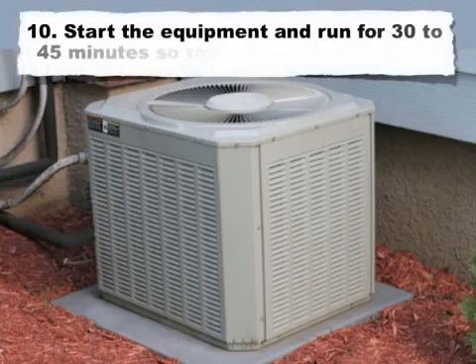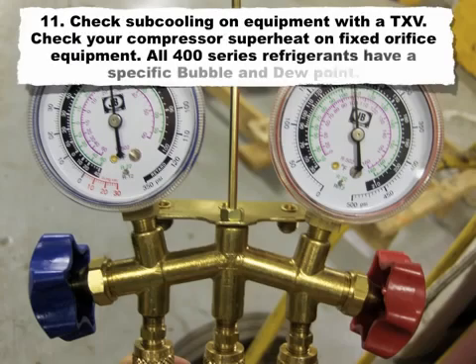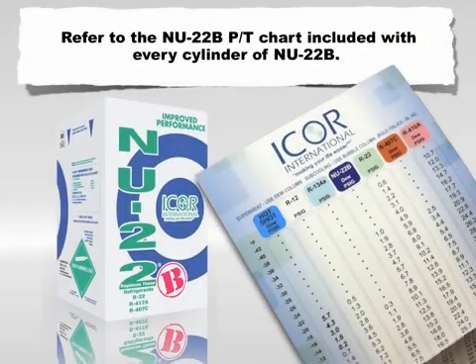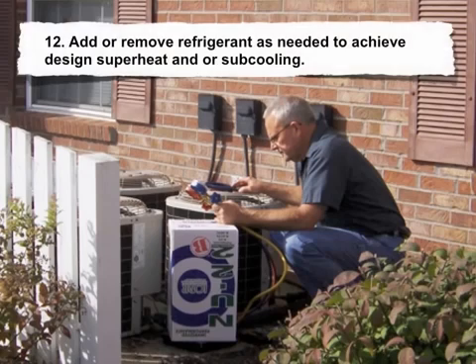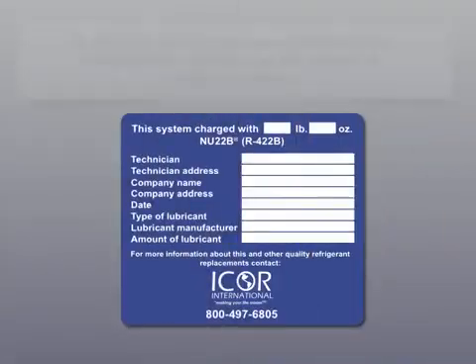Step 10: start the equipment and run for 30 to 45 minutes for the system to stabilize. Step 11: check subcooling on equipment with a TXV; check compressor superheat on fixed orifice equipment. Note that all 400 series refrigerants have a specific bubble and dew point — refer to the NU-22B PT chart included with every cylinder of NU-22B. You can also download a PT chart at www.icorinternational.com or from the mobile site icor.mobi. Step 12: add or remove refrigerant as needed to achieve design superheat and/or subcooling. Step 13: check the pressure safety controls and condenser fan cycling control for proper setting. Step 14: properly label the equipment with the new refrigerant designation and the amount of refrigerant charge. Step 15: record post-conversion data.